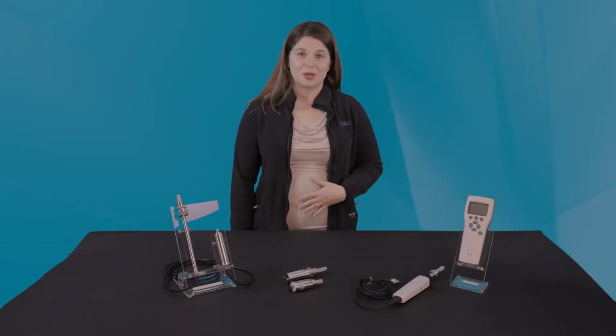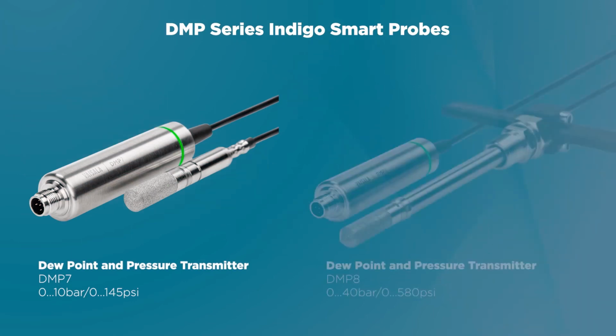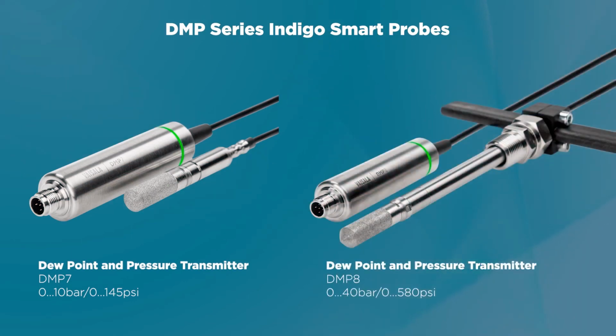Now, what if you're monitoring a process where it would be valuable to know not only dew point, but also the process temperature and other moisture-related variables? In this case, you'd want to consider our high-end dew point probes, the DMP series Indigo Smart Probes. The DMP7 and DMP8 probes are both ideal for this sort of measurement, with the DMP8 being the most robust solution, with a pressure rating up to 40 bar or 580 psi, and adjustable insertion depth for flexible installation. These probes are functional as standalone probes providing a Modbus RTU output, or they can be combined with an Indigo transmitter for a display, analog and Ethernet outputs, and dual probe monitoring, among other features.